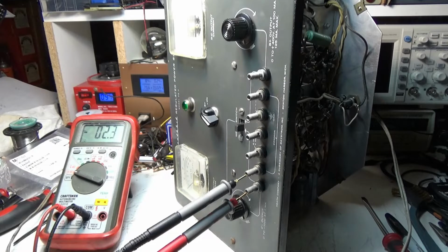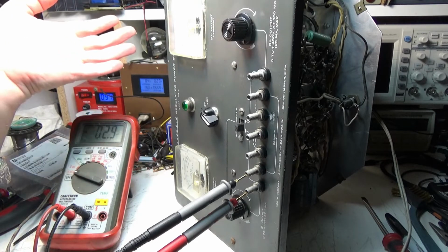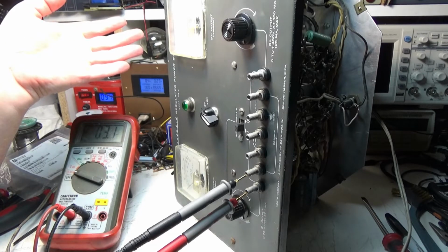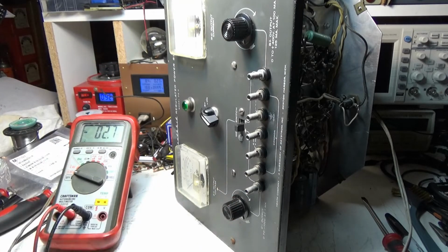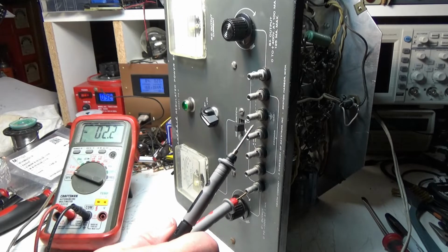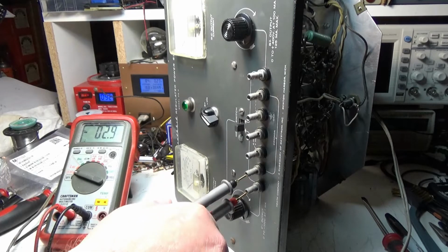20 watts. Yeah, I'm pretty sure there's a capacitor shorted. The only thing that really should be drawing any voltage or amperage right now are the heater elements in those tubes. My meter is drawing amperage. 0.23, so I'm pretty sure we got a bad capacitor in there.